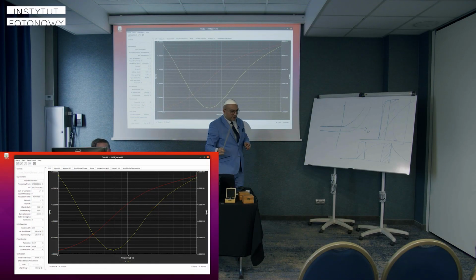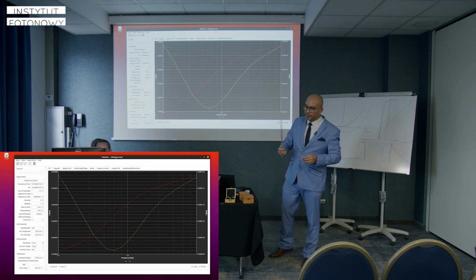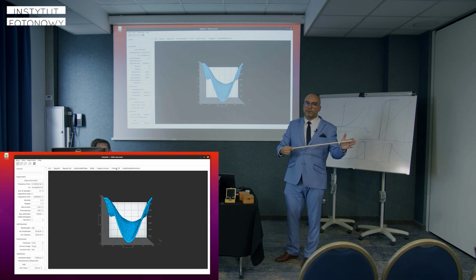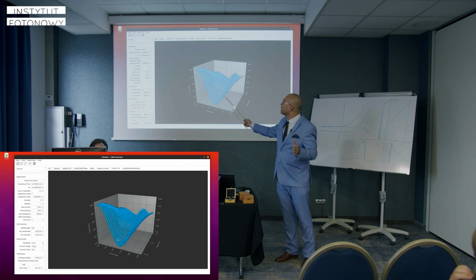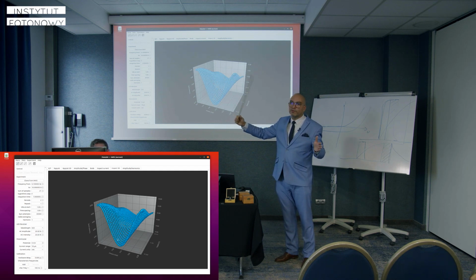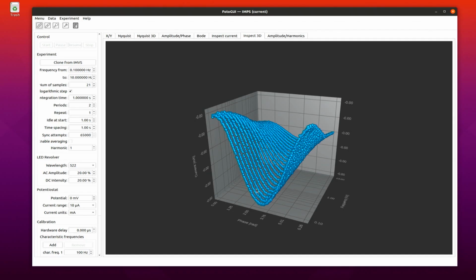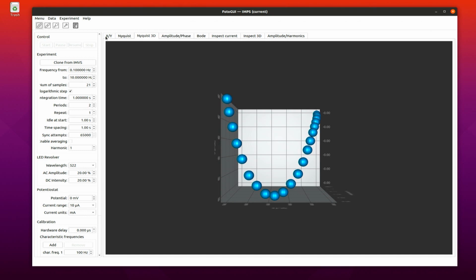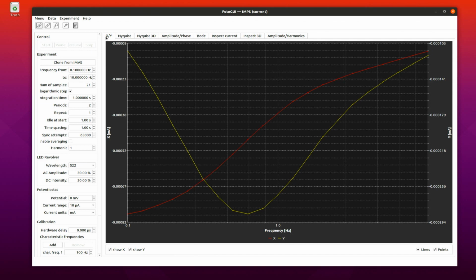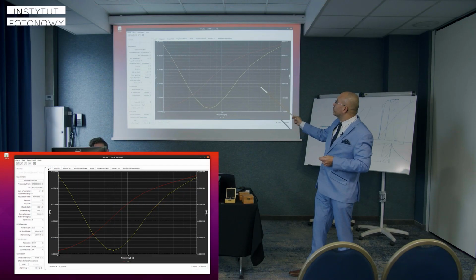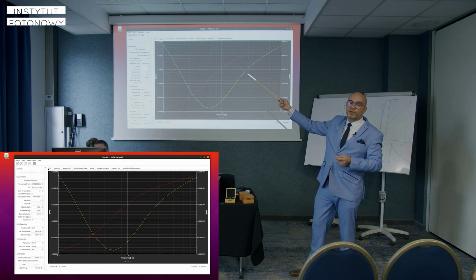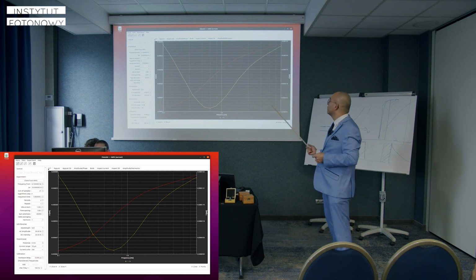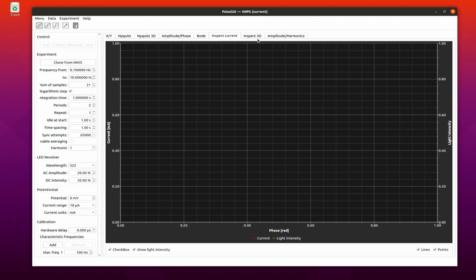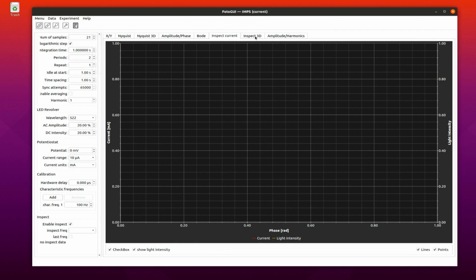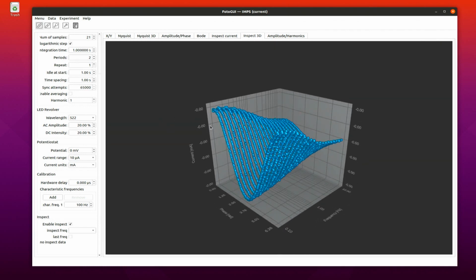We can handle very slow samples with frequencies down to some millihertz or microhertz. So to record one full period in case of 0.1 hertz, we need 10 seconds. If we start from 0.01, then for one full period we need 100 seconds, and to respect your time, we are not going to perform a whole experiment, so we just uploaded some previous results. All results that you are measuring, you can save to file and then upload again for study. And here you can see all the results.